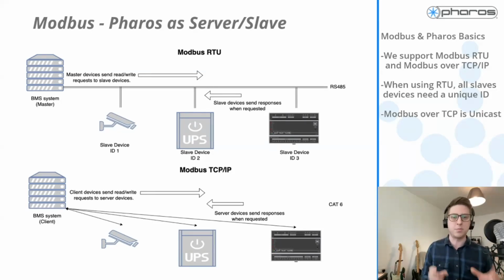But as I said, the module itself, the actual programming that you would use within the module, is pretty much exactly the same thing. There is, however, a slight difference in some of the terminology used between the Modbus RTU and the Modbus TCP version. This is just how the protocol itself is written. This is not a naming convention that we've used, but Modbus RTU describes a master and slave relationship. The Modbus TCP version describes a client and server relationship.